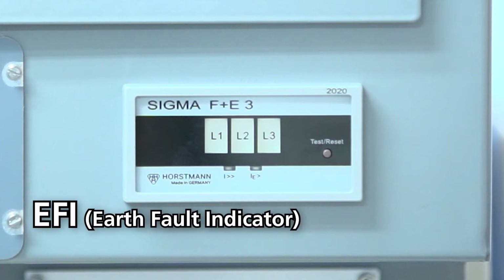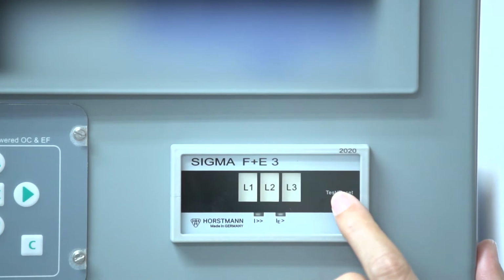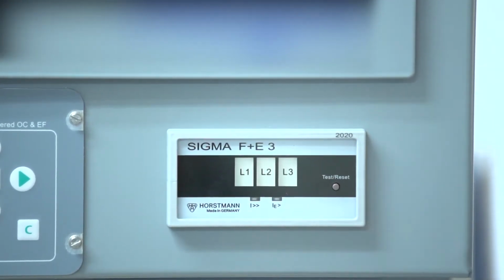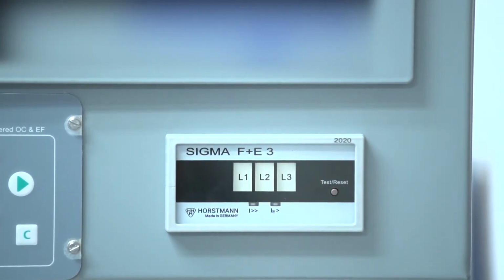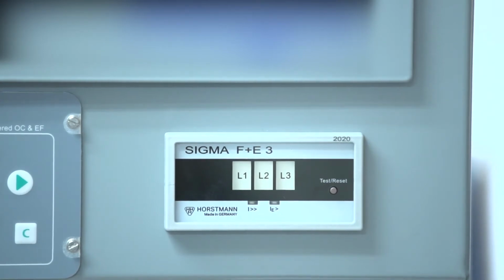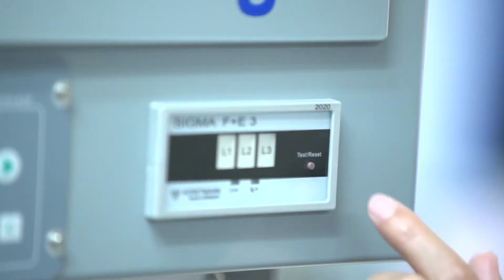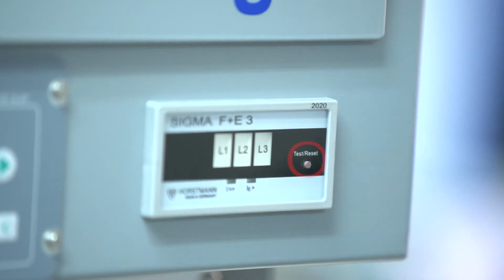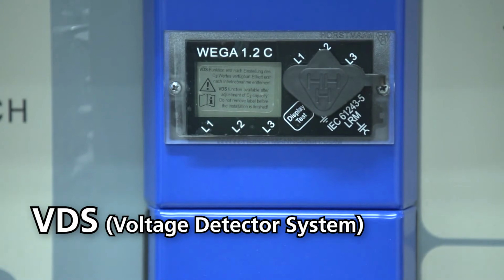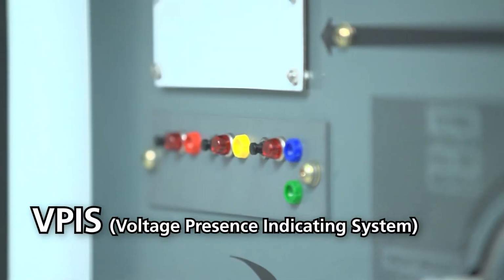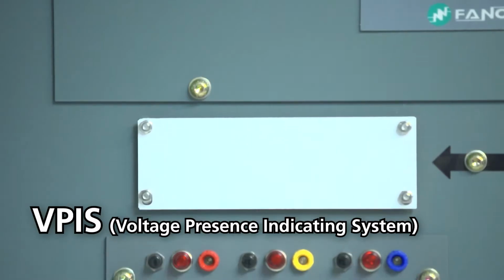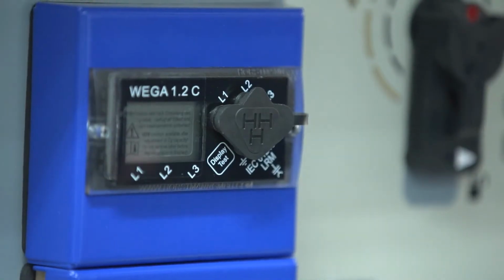An EFI, earth fault indicator, detects faults at the incoming or line switch. When a fault occurs, typically a red light will be shown on the product to notify users. The users can then inspect the line or cable, clear or repair the fault in their system, then press the reset button on the EFI.